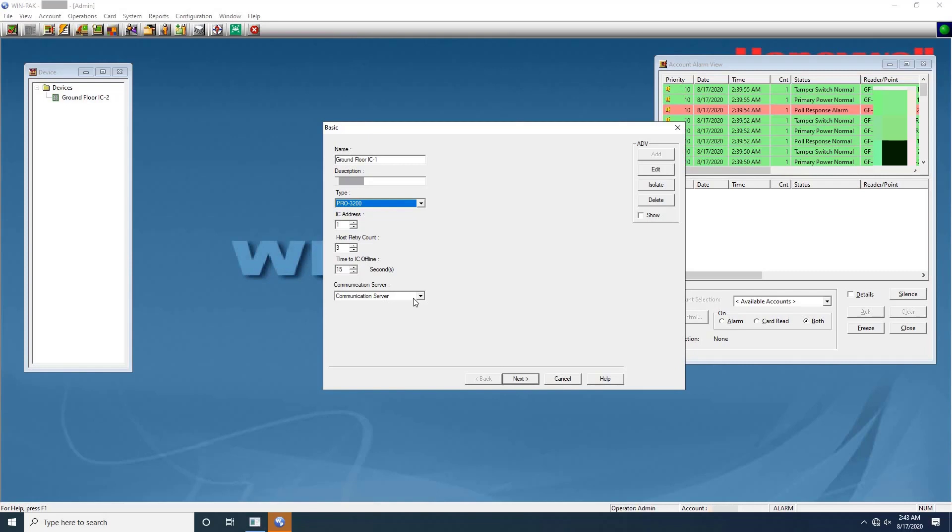Next enter the value for time to IC offline. This is the maximum time allowed for the software to declare the panel as offline when there is no response from the intelligent controller. The time to IC offline can be set from 10 to 65 seconds, 15 seconds is the default. A range of 10 to 30 seconds is recommended for most applications. Here also I'm not changing the default value. Select the communication server from the list. But if you have single server, it will take default that server, so no need to change it. Once finished this setting, click next to configure the connection settings.